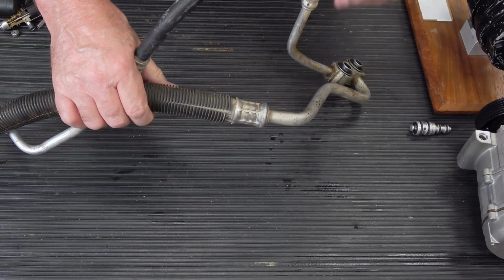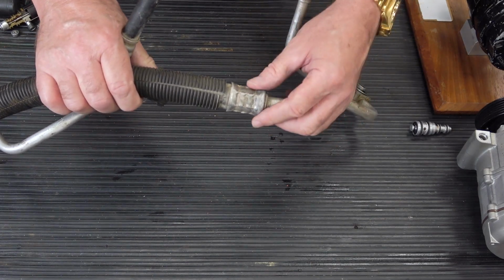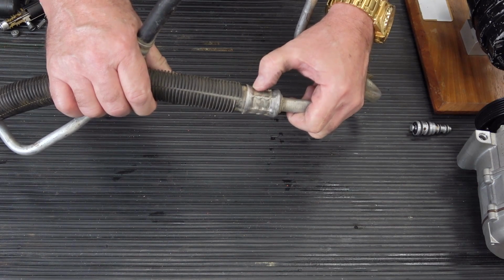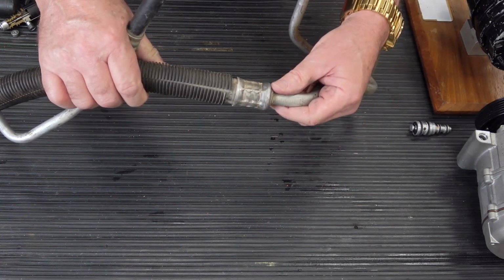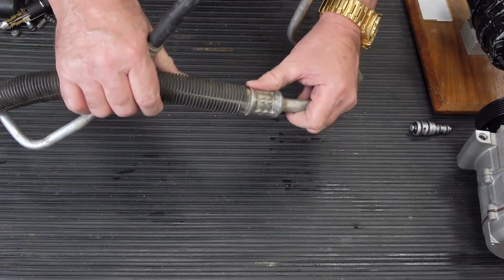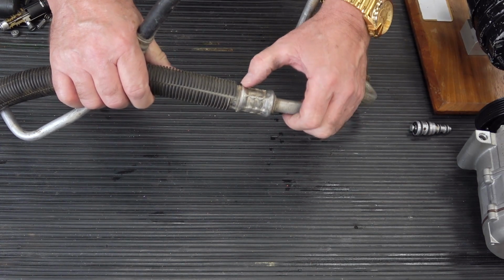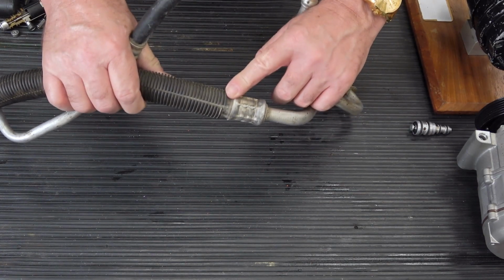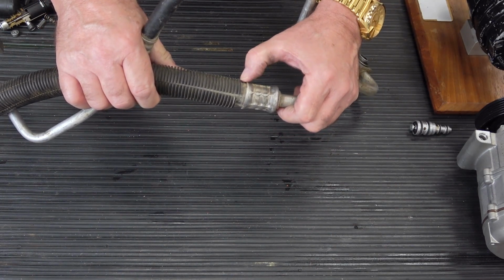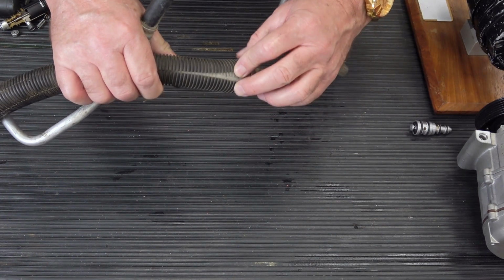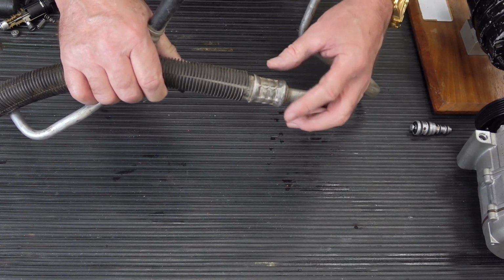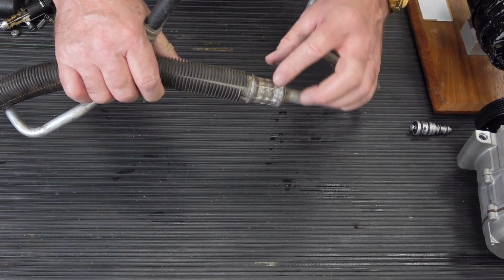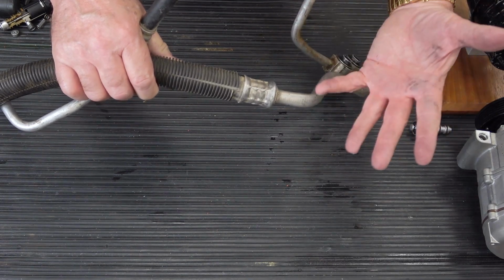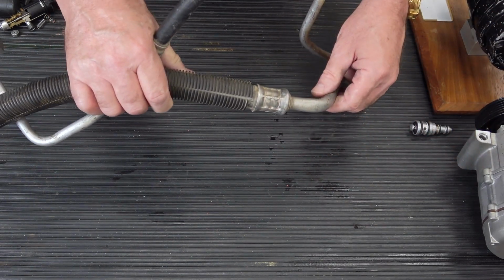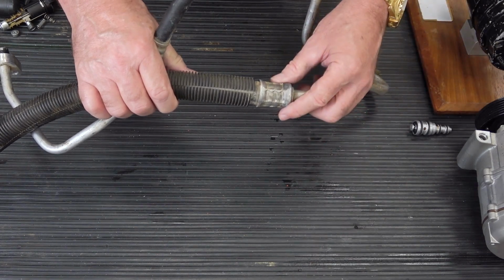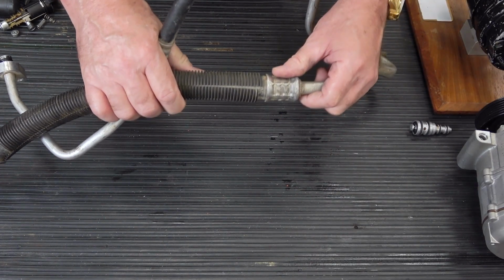However, when you consider that rubber is organic, oftentimes the micro leak that led to the low charge, oil dropout, and no compressor lubrication... In other words, often the root cause of the original compressor failure is a micro leak at some of these crimps here, right? And if there's a leak here, especially if the compressor is cracked, you might not be able to leak check this crimp until you've flushed the system, put the whole system back together, and now at the very end you get to leak check this crimp.